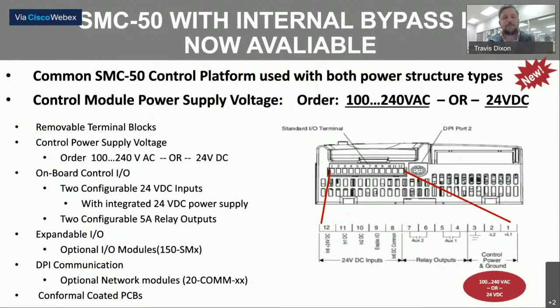And also is the common control module to both the internal bypass and external bypass, and solid state, excuse me. You can get it with a 100 to 240 volt AC supply or 24 volt DC. You get your onboard control IO, 2 configurable 24 volt DC inputs with integrated 24-volt DC power supply, and you get 2 configurable relay outs that are rated up to 5 amps. You also get the expandable I/O slots up to three cards, and all the different communications modules associated with that.